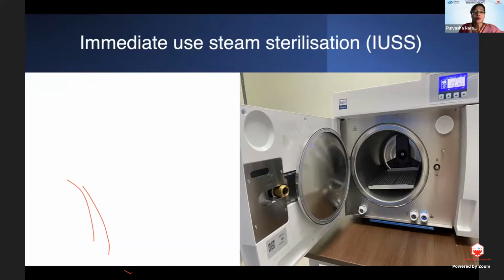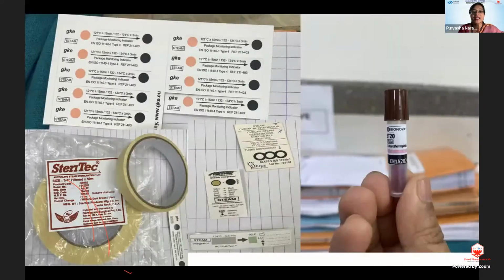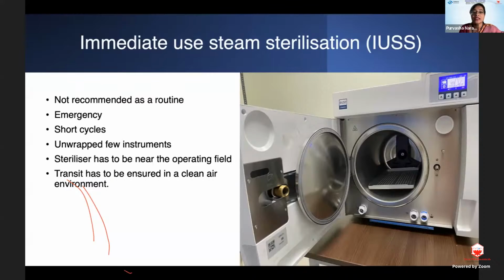A word or two about the flash autoclave or the immediate use steam sterilizers. Yes, they are there, but they were not built exactly for ophthalmic use. They have more use for dental and other ENT surgeries. And for us, it is basically not recommended as a routine. These are only to be used as an emergency measure, just in case an instrument falls off while doing surgery, or something critical has come up, or some rep has got your instrument immediately and it has to be used. Only in those cases, an unwrapped instrument has to be put in these and sterilized accordingly, and it has to be in the operating theater itself, and it should not have a very large transit time or area or environment. So it basically has a very limited role, but it is sometimes essential in emergencies.